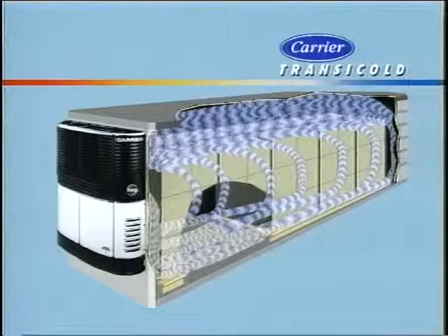The override temperature comes from the factory set for 11 degrees and can be adjusted by a refrigeration shop between 4 and 18 degrees. After the minimum off time, the unit will restart if the temperature is more than 3.5 degrees away from set point. The auto start-stop mode works well to conserve fuel by allowing the engine to operate only when needed. The off time can be changed from the factory setting of 20 minutes to between 10 and 90 minutes. This timer can be adjusted by most refrigeration shops.